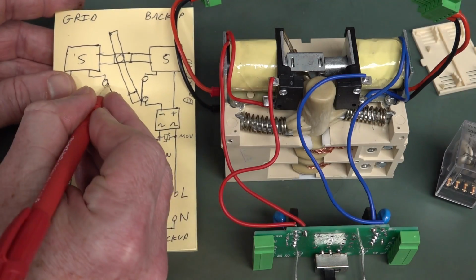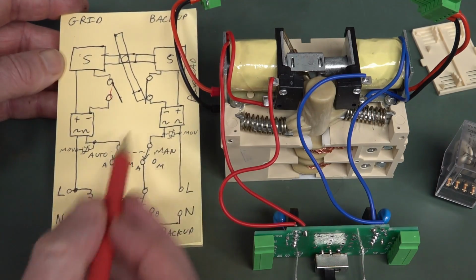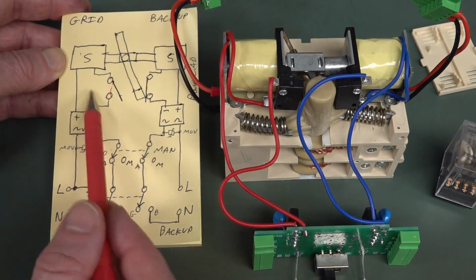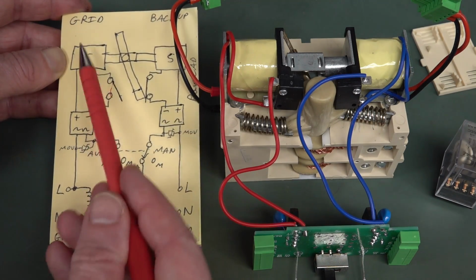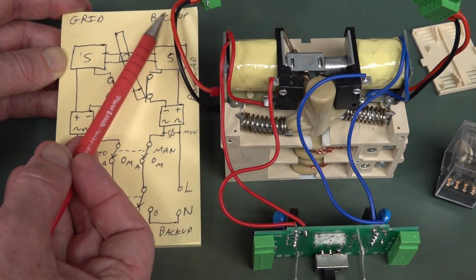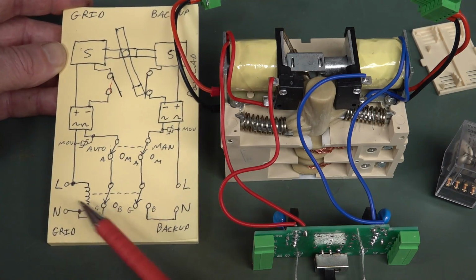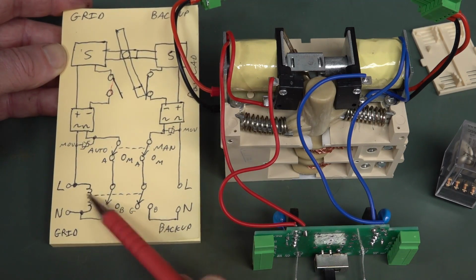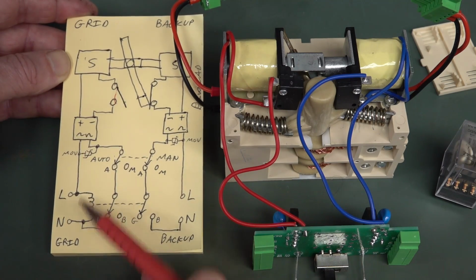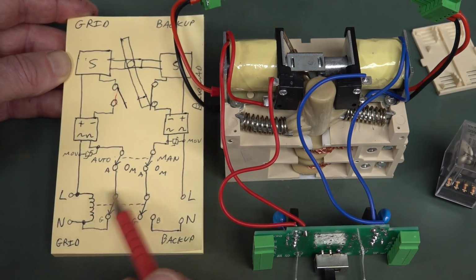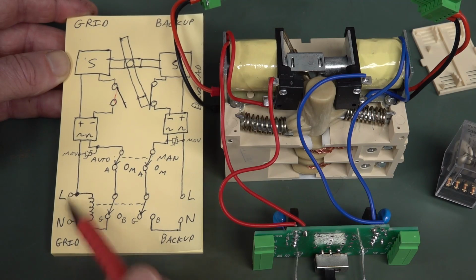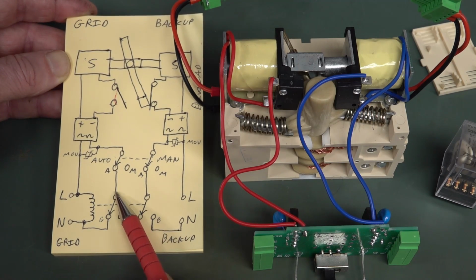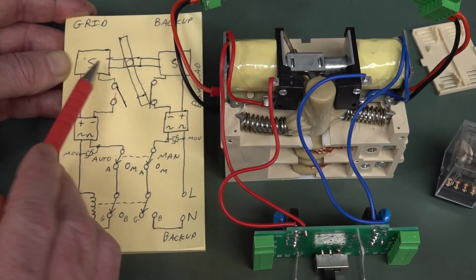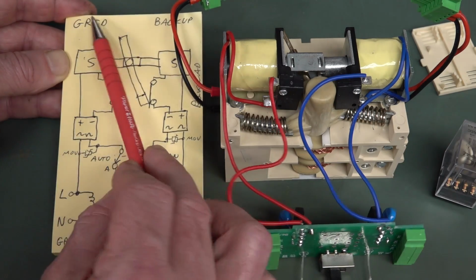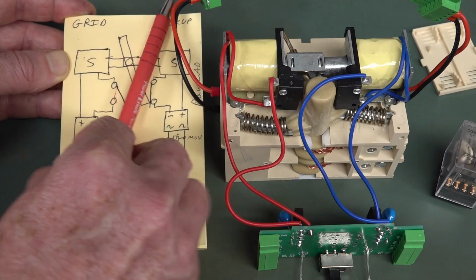So this micro switch is now closed like this, and this solenoid is sitting here waiting. Oh, come on, give me power, so I can switch from the backup back to the grid side. And of course, because this is the priority power source, it has the relay coil on it. So as soon as the line workers are finished fixing the grid, good on ya, champs, then it applies power back onto here, and the relay flips back, and then this solenoid activates very briefly, and it goes clunk back into the other position, and it's reset itself.